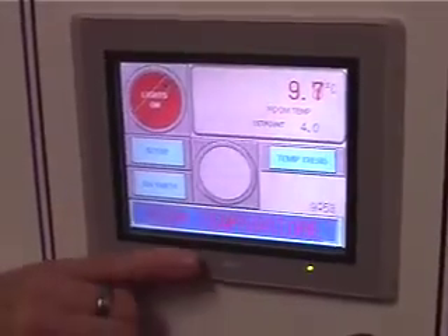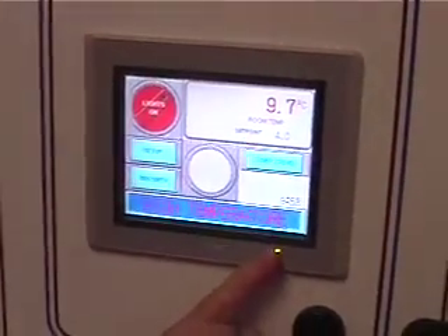Now, because of all the alarms on it and issues that can be on the status line, it may take a little time to rotate through. But this will come up pretty quick on the first shot. If you've got more than one thing like this, and it was a water failure that was causing the issue, it may take 10 or 15 seconds to actually rotate through that, tell you it's a water failure. So if you say there's a problem with it, I may ask you to just sit and watch that for a second, see if it scrolls through and tells you something other than just high temperature. Sometimes it will.